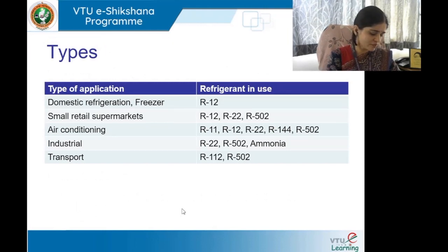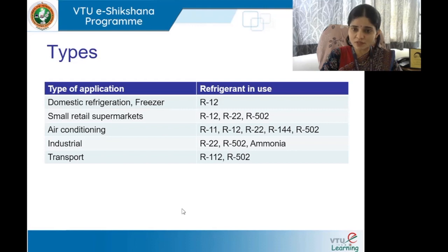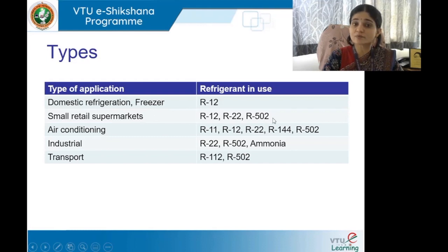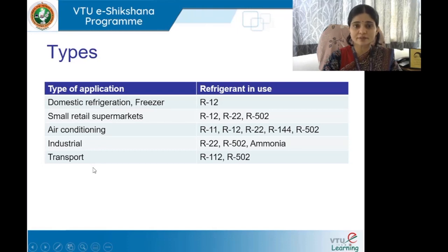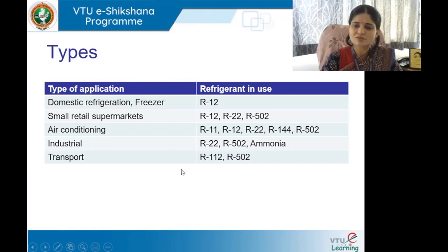A table provides an overview of refrigerants and their applications: R12 is used in domestic refrigeration and freezers; R12, R22, and R502 are used in small retail and supermarket refrigeration; R11, R12, R22, R114, and R502 are used across various scales of air conditioning systems; ammonia is used in industrial processing and refrigeration — though it is confined to industrial use due to its strong odour; and R12 and R502 are used in transport refrigeration.